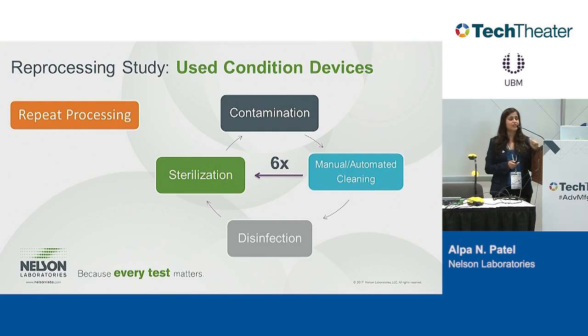Now, when we do a use, it has to be contaminated as it would be for the validation. It would have to be cleaned manually or automated, and either you go through disinfection or you go through sterilization. One or the other has to happen, and that is a full life cycle of the device and how it would be reprocessed at the healthcare facility.